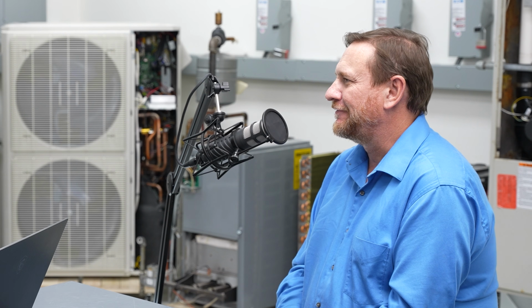Because that's my first thing: when that blower comes on, it means we're changing how that flame is burning. And that's my first concern. So before moving on, I'd say, hey, let's find out how we've identified that. And me personally, I like to see combustion analysis. I think anything that we work on with a gas furnace, for reliability reasons, we should be doing combustion analysis so we know how that system is actually working.